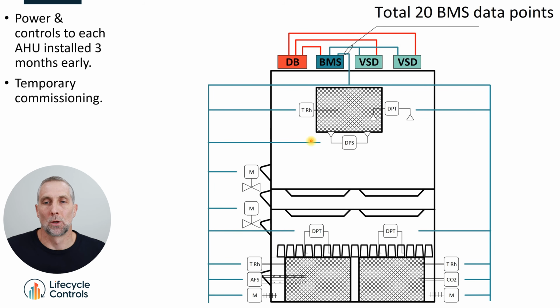So here's our air handling unit. Months and months in advance of it normally being installed, you just roll up to the AHU with a trolley, you screw the 2 VSDs onto the AHU, this BMS control panel with this one controller in, this little distribution board, and you can start pre-wiring a lot of this AHU now because you're not wiring back to a central location very far away. And if you're buddies with mechanical and you say, listen guys, can you just please put a meter of pipework, get the heating and cooling valves installed for us earlier than you would normally have, please? Then we can wire our 24 volts AC and our 0 to 10 volts DC signals to the actuators. Maybe you could try to get the outside air damper and the minimum outside air dampers installed. You put the actuators on. So you get your supply air temperature, pressure, humidity, return air temperature, CO2, volume, airflow stations, the whole thing, right? Get that all roughed in there.